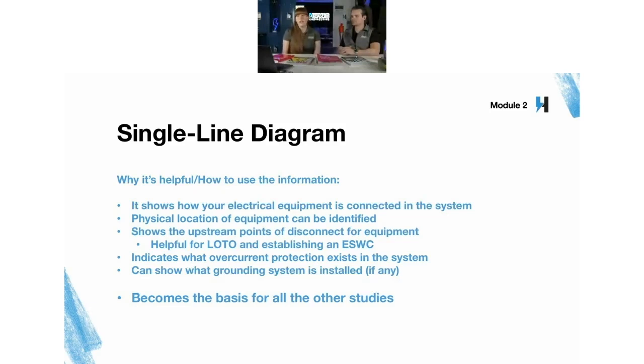It also can indicate what overcurrent protection you have in your system, like breakers, fuses, relays, that kind of stuff. And it can show what grounding system is installed, if any, if that's included on the one line. It's not typical, but I've seen people include the ground and the neutral in a single line diagram.